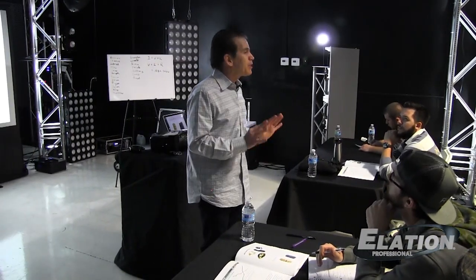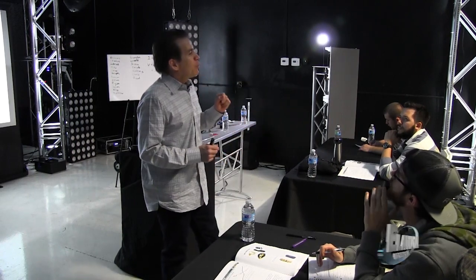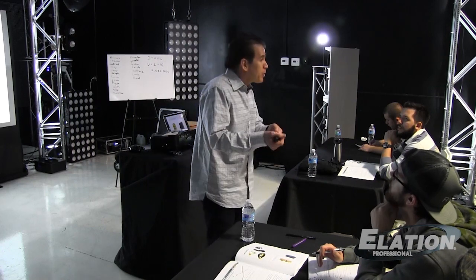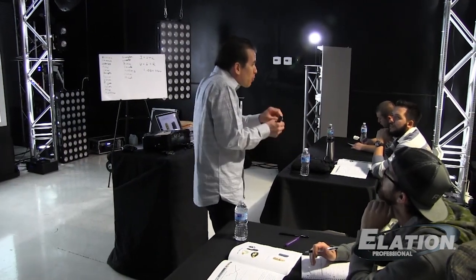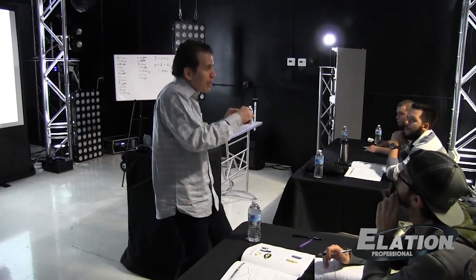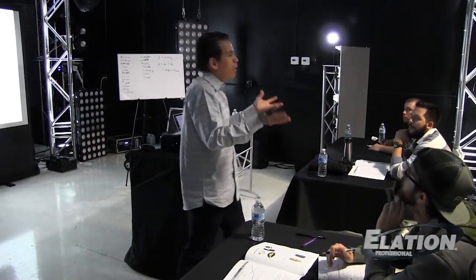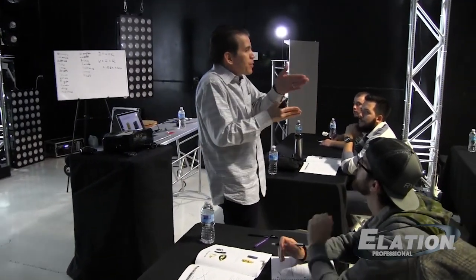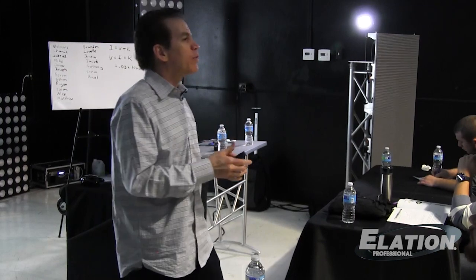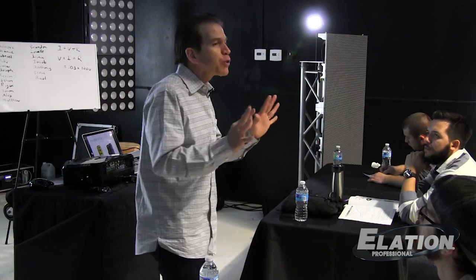Those UPS units do not have GFCI protection on them. Honestly, it may be difficult to plug a UPS into a GFCI, because the way a UPS draws current isn't a normal sine wave, it's usually in pulses, which means a GFCI reads that as leakage current and will probably trip. So my recommendation is to try it out, see if you can get it to work with a portable GFCI, and if you can't, here's what you do.